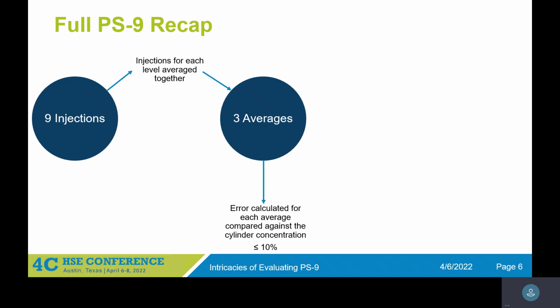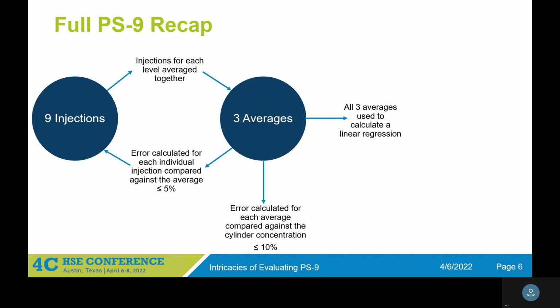Then from there, we calculate the error against the cylinder concentration and make sure that's less than or equal to 10%. What we then do is retroactively take those averages back and compare each one against the 3 injections that were done at that level, and make sure that's within 5% of the average. And then lastly, all 3 averages are used to calculate a linear regression.